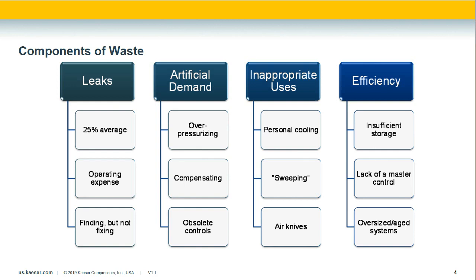Inappropriate uses occur any time you're using compressed air when an alternative means could achieve the same effect. A big example is employees using compressed air for personal cooling when fans would be far more efficient. The efficiency slice — 50% — is where you can improve the most by addressing problem areas within your compressed air system, including insufficient storage, lack of a master controller, and inherent system design inefficiency.